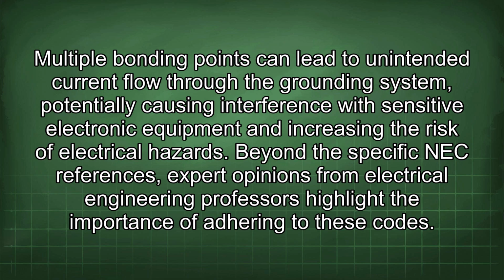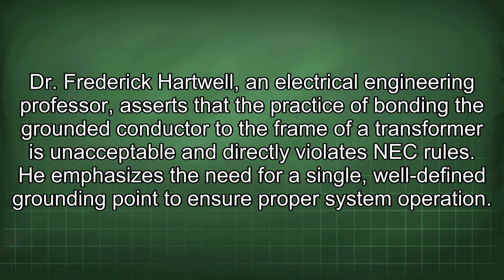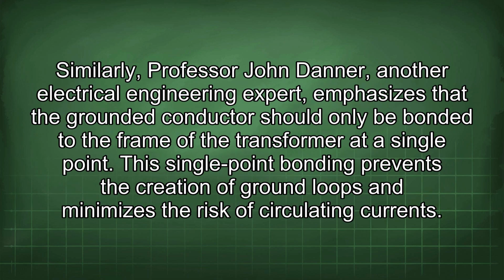Beyond the specific NEC references, expert opinions from electrical engineering professors highlight the importance of adhering to these codes. Dr. Frederick Hartwell, an electrical engineering professor, asserts that the practice of bonding the grounded conductor to the frame of a transformer is unacceptable and directly violates NEC rules. He emphasizes the need for a single, well-defined grounding point to ensure proper system operation. Similarly, Professor John Danner, another electrical engineering expert, emphasizes that the grounded conductor should only be bonded to the frame of the transformer at a single point. This single point bonding prevents the creation of ground loops and minimizes the risk of circulating currents.